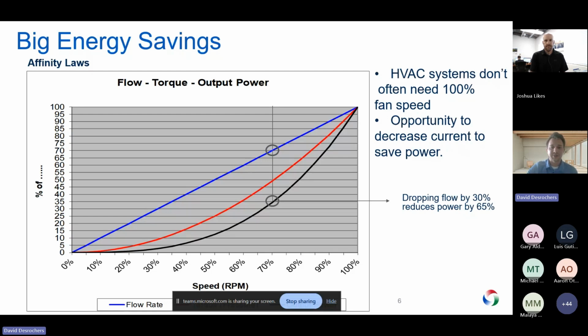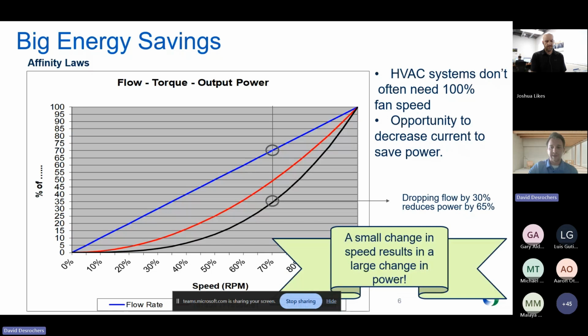This is just due to the dynamic nature of forcing an impeller or a blade against a moving fluid like water or air. And it's just a characteristic of most centrifugal pumps and fans. So the VFD takes full advantage of that. When you're backing off speed just a little bit, you get a large reduction in electrical usage. Over time, this obviously correlates to large savings on cost. And this is why VFDs have been incorporated into HVAC systems for decades now, and they've become very reliable at doing so. So, big takeaway again, small change in speed results in a large change in power for VFDs.